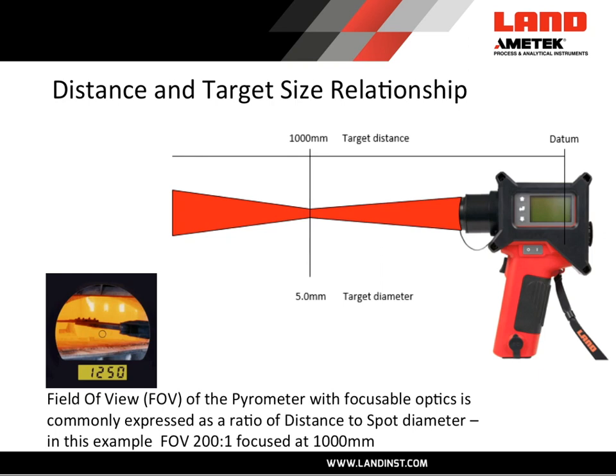In this example we have a portable pyrometer with fully focusable optics, and the pyrometer field of view is expressed as 200 to 1. That means every 200 units of distance you go away, the target diameter grows by one unit. In this case somebody has focused at a distance of one meter — 1000 millimeters. Dividing that by 200 gives a target size of 5 millimeters. With this pyrometer there is through-the-lens sighting so you can see where that target spot is and also how large it is.